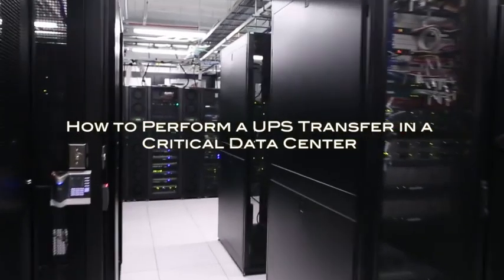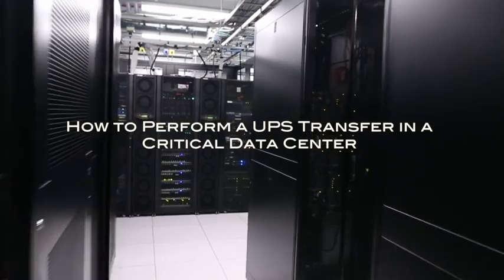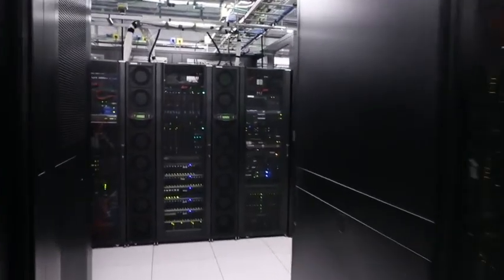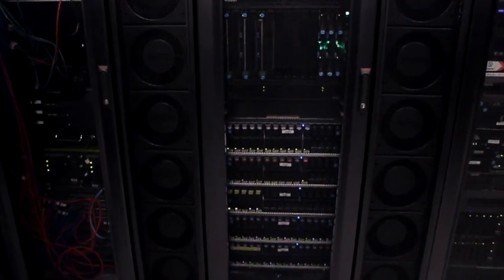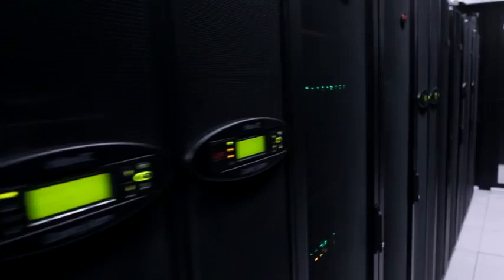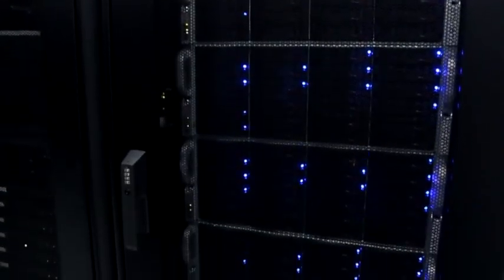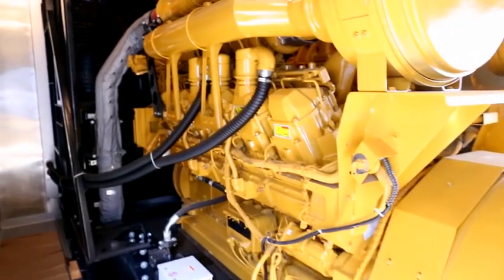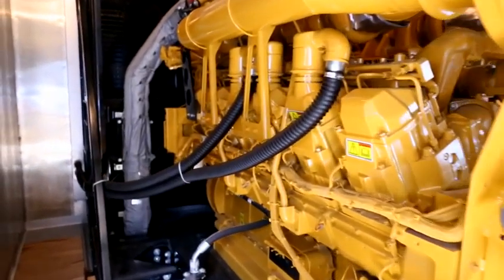Technology systems operating in data centers are routinely notified of maintenance requiring uninterruptible power supply (UPS) system transfers. IT frequently understands these transfers are reason for concern, but may not understand the specifics of the event. This video is an example of a typical process to transfer the IT load from utility power to generator power, which allows technicians to safely perform maintenance on the UPS.